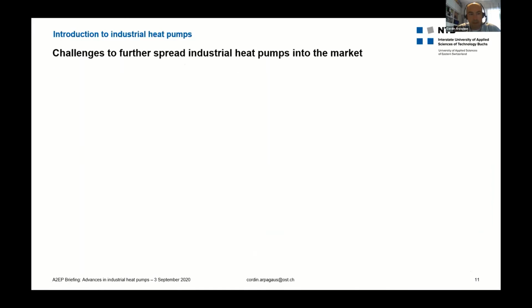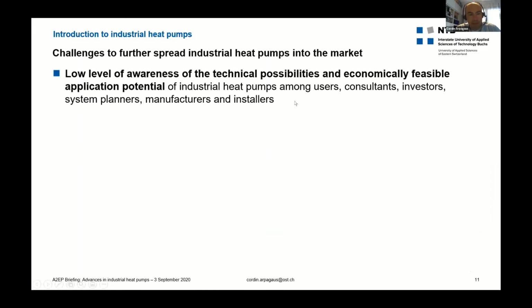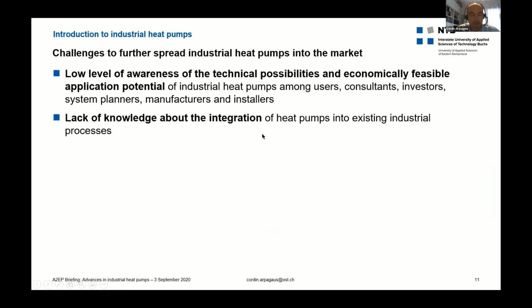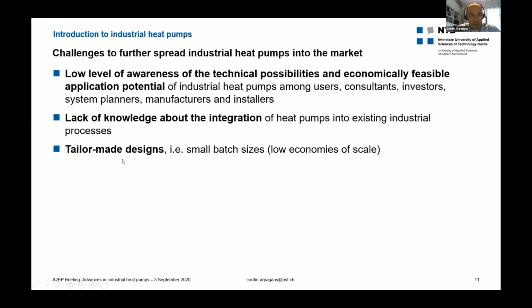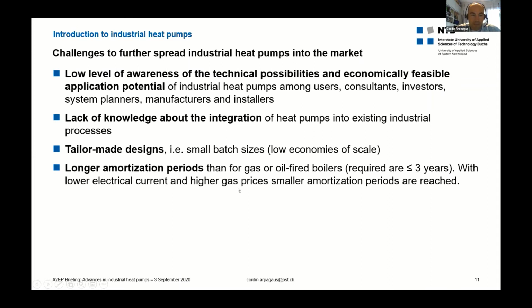So there are several challenges to the wider spread of industrial heat pumps in the market. First is quite a low awareness of the technical possibilities which are there with heat pumps. There's also a lack of knowledge about how to integrate a heat pump into systems. The bigger heat pumps are also quite tailor-made designs, meaning batch sizes are small, giving low economies of scale. Compared to an oil-fired boiler, the amortization periods are sometimes challenging - typically 3 years are required, and this depends strongly on the local electrical price and gas price.